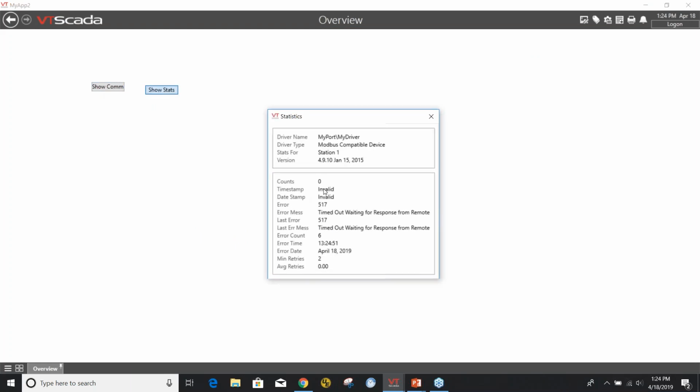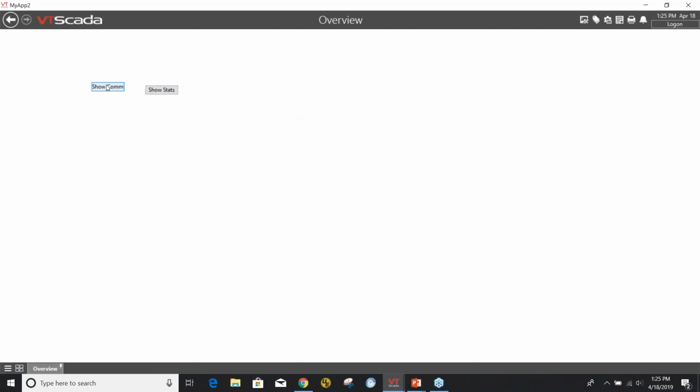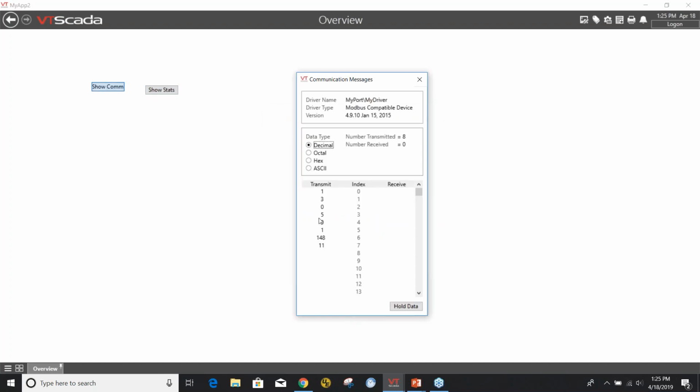So we look and we say, okay, we got an invalid timestamp. We have an error of 517, timed out waiting for response. And we can see our count is going up every second or a couple of seconds, indicating that we're continuously failing. Okay. I go over to my comms now and I can see that I'm transmitting out data and I'm receiving no data back. Okay, so this all kind of falls into place with one another.